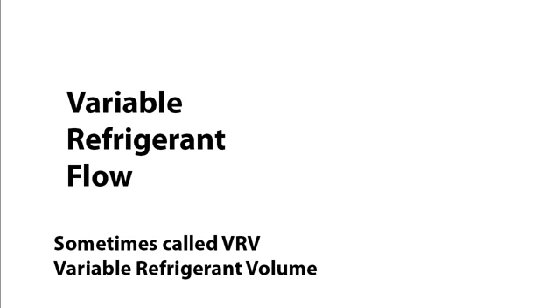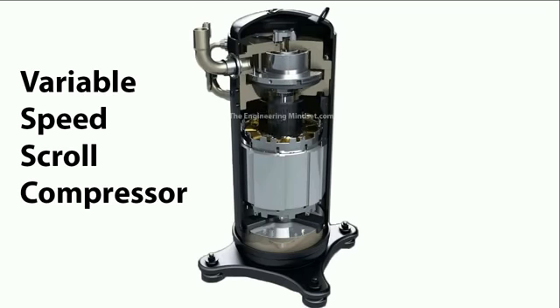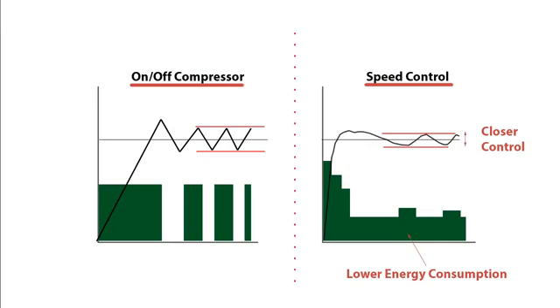It pretty much just varies by manufacturer on the title which they use, but both acronyms relate to this slightly complex version of a HVAC refrigeration system for buildings. Now the reason these units are called variable refrigerant is because the unit is able to modulate the amount of refrigerant that flows through the system. It uses a variable frequency drive to alter the speed of the scroll compressor. This is very energy efficient as the speed is reduced to match the exact requirement.